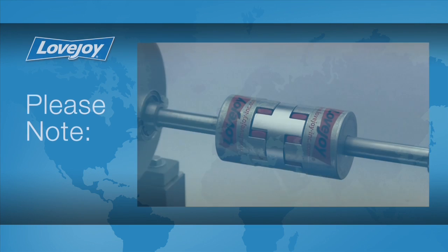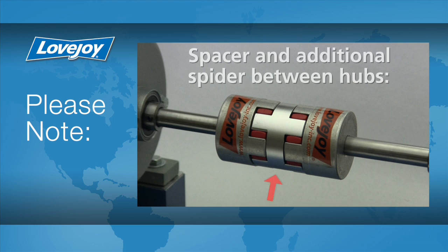The CJ SPC curved jaw coupling is very similar to the standard curved jaw coupling with a spacer and additional spider added between the hubs. This allows the CJ SPC coupling to span a larger gap than the standard curved jaw coupling while offering a slight increase in the amount of parallel misalignment the coupling can accommodate.